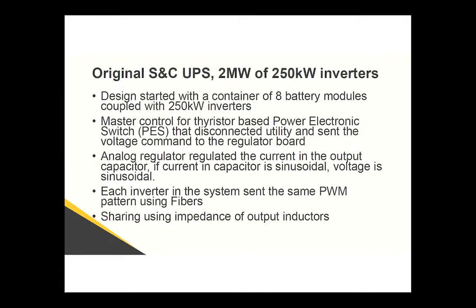When we saw a problem with the utility, we would open the switch and run the inverter to cover the load. It used an analog voltage regulator, and in order to control the 8 inverters, we sent the same switching signals to all 8 inverters. So each one was getting those through fiber optics, and we got sharing between the various inverters using output inductors.